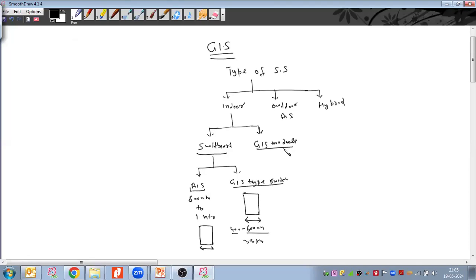We also discussed yesterday that in the outdoor there could be two types. It could be the conventional outdoor AIS type substation, and the outdoor GIS is also available. Sometimes in a project, when we want to minimize or avoid the building civil cost, because we make a building to place the GIS module indoor, some companies take outdoor GIS. In that case the building is not required, so civil cost is saved.